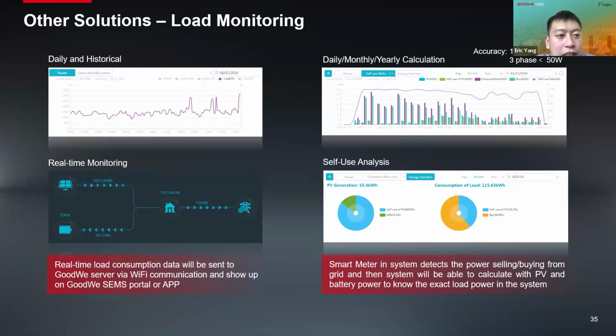And these are some other solutions, for example, load monitoring, because in this storage inverter system, the customer mainly focuses on the load consumption and also the monitoring. They want to know whether the load power comes from PV, the battery, or the grid, and also the percentage. In the GoodWe SEMS platform, we have this kind of data. At the left side, we have the real-time load consumption. This is the real time. And at the right side, we have some calculations and also analysis of the system.